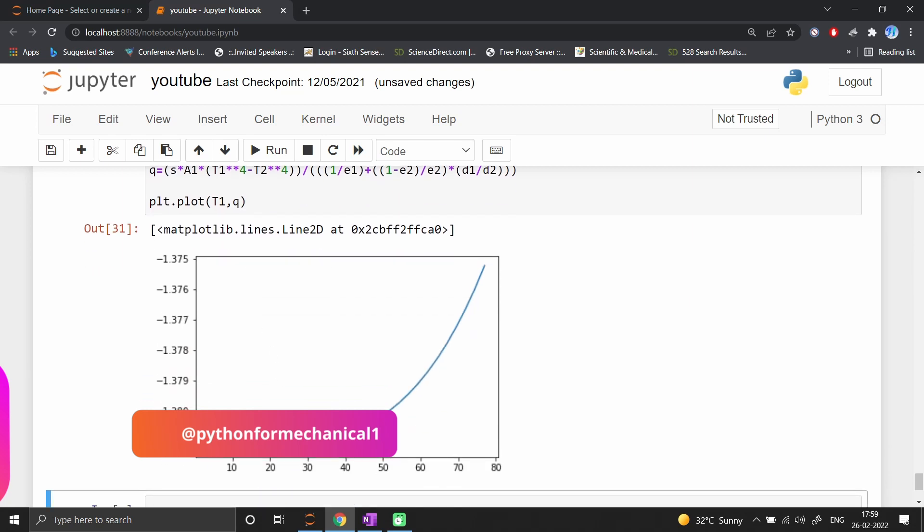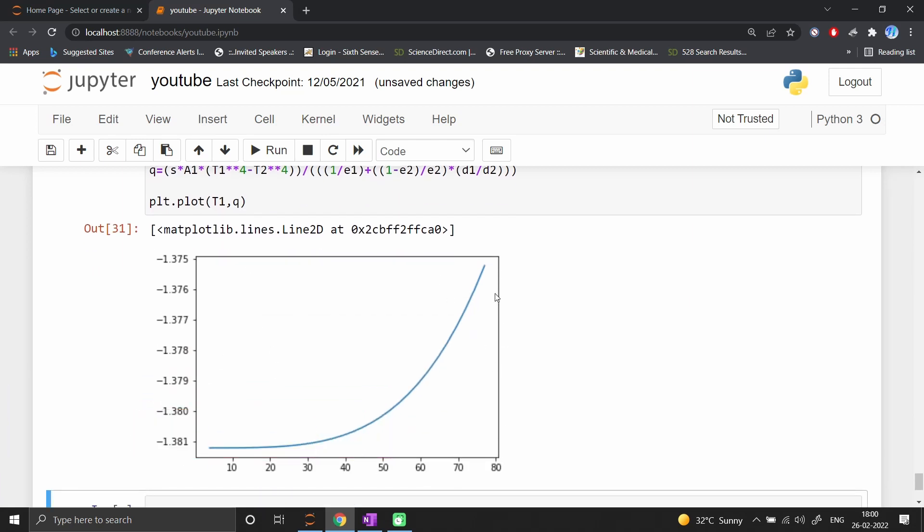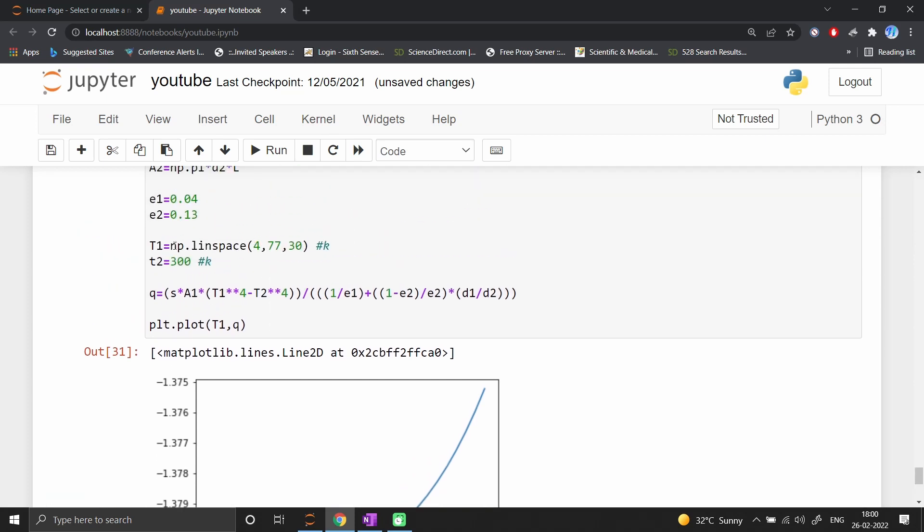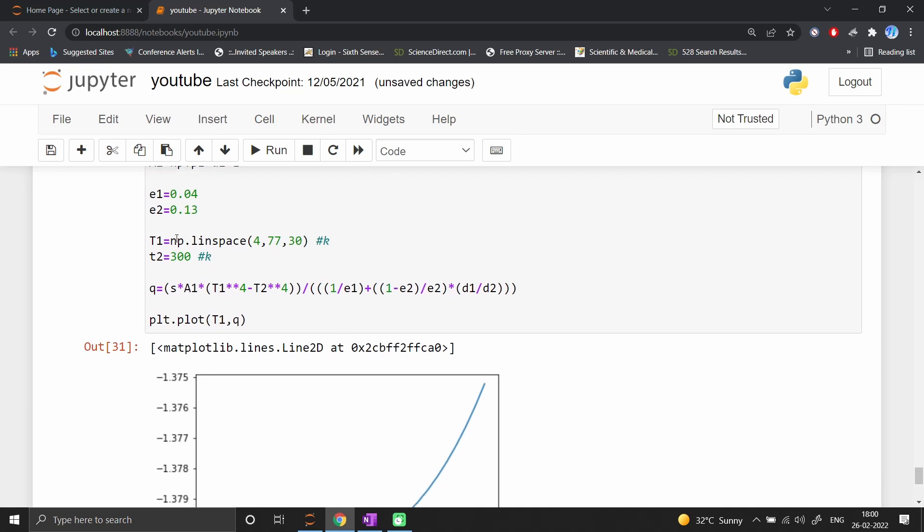You can see the heat load is smallest at 77K and maximum at 4 Kelvin. Around 20K it becomes flat, so heat load doesn't increase much after 20 degrees by radiation.